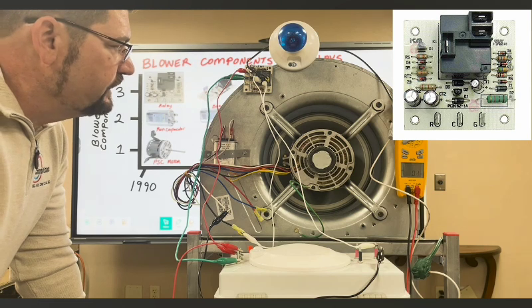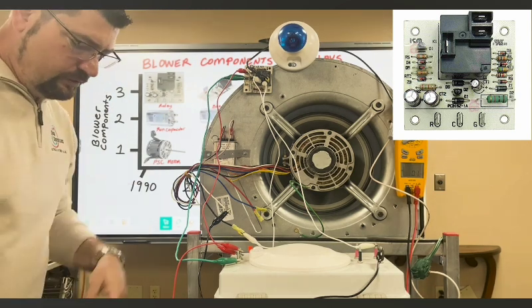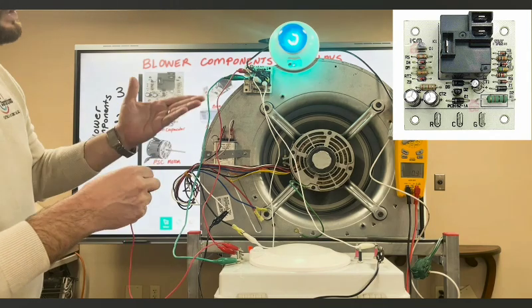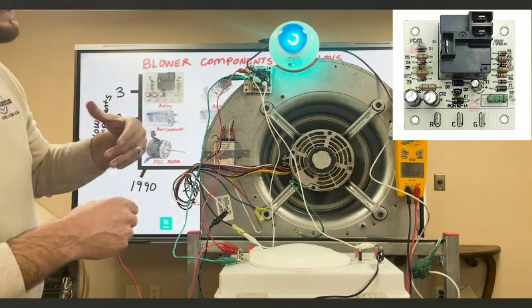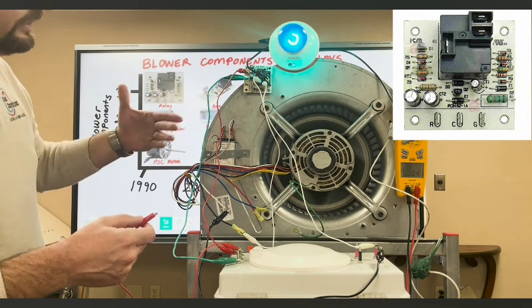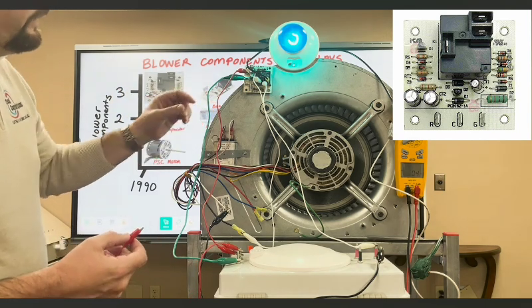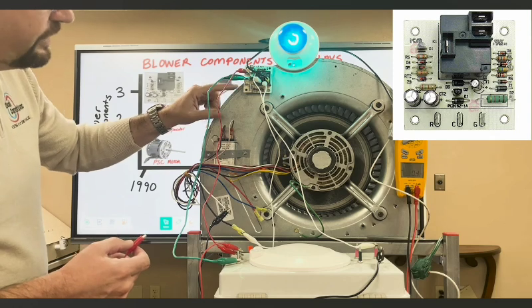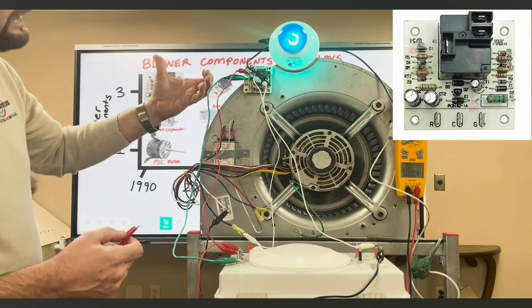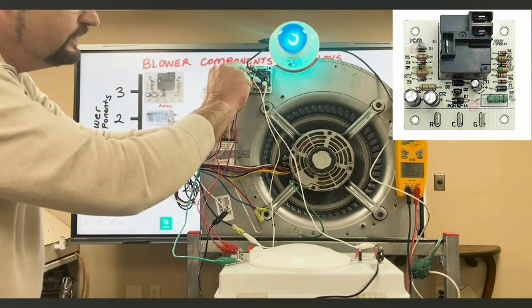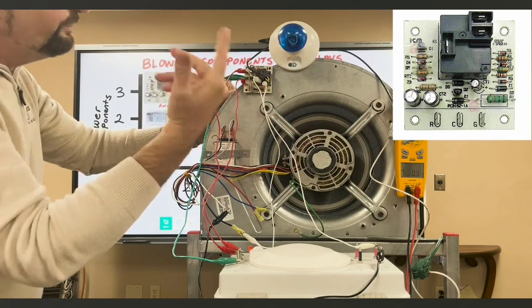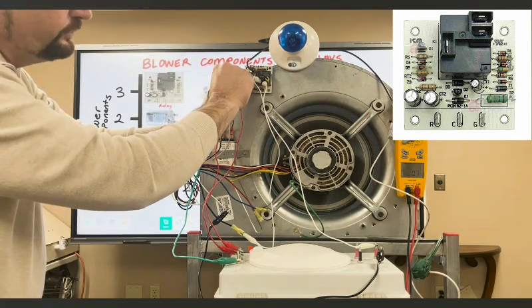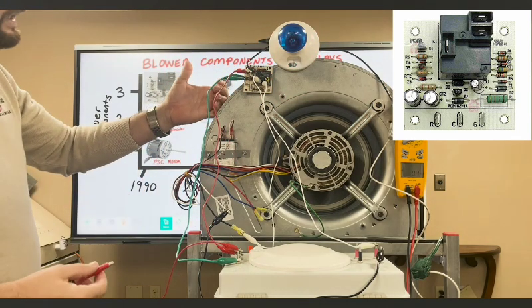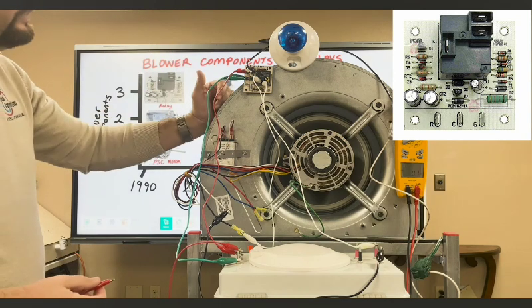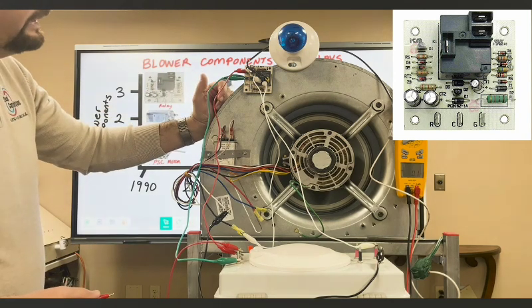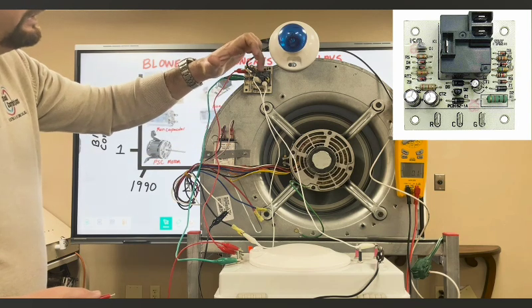I like to use the timer because let's just say that this motor was giving me an issue. I would put my timer out there, and if I knew it was possibly running for maybe 5 or 6 minutes before I got to it, and I could identify that there's no 24 volts between common and G and it's still running, I'm still going to get my timer out, and I might even toggle it a few times and see if I can get it to mess up on me. So I would simply put 24 volts on it, remove 24 volts, use my timer on my phone. I would see if I had a 50-second off delay, and if it was still running, sometimes you can just give it a little click.